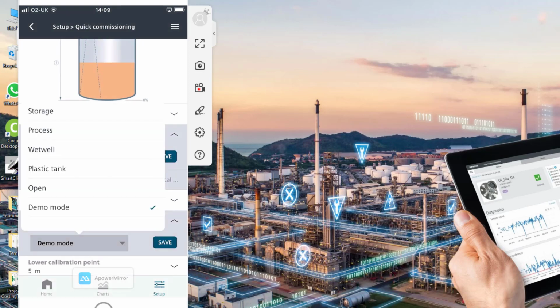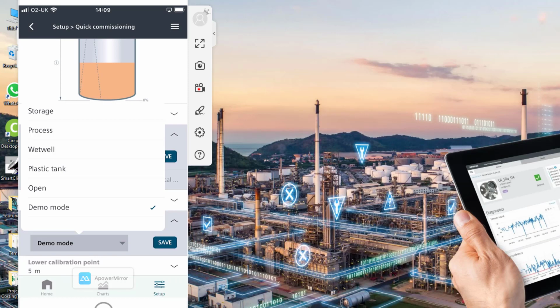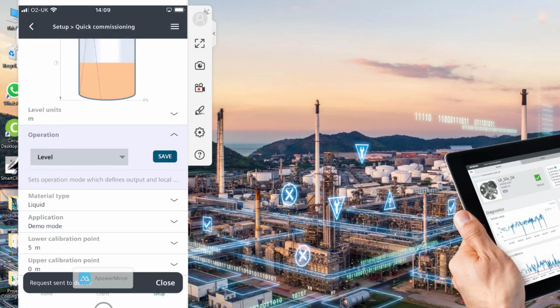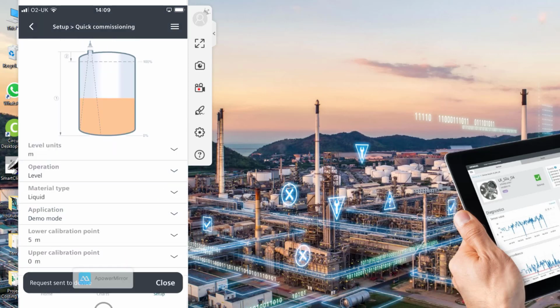We have demo mode. Now these settings affect how the radar reacts to different changes in process. A lot of these could be slow moving, so if you have it on storage, that could be slow moving. You don't want the level to jump to a false echo straight away, so there's a lot of filtering in there to stop that from happening. In demo mode, we've virtually got no filtering, so I'll leave it at that for what we're doing. When you click save, that's when it writes it to the device.